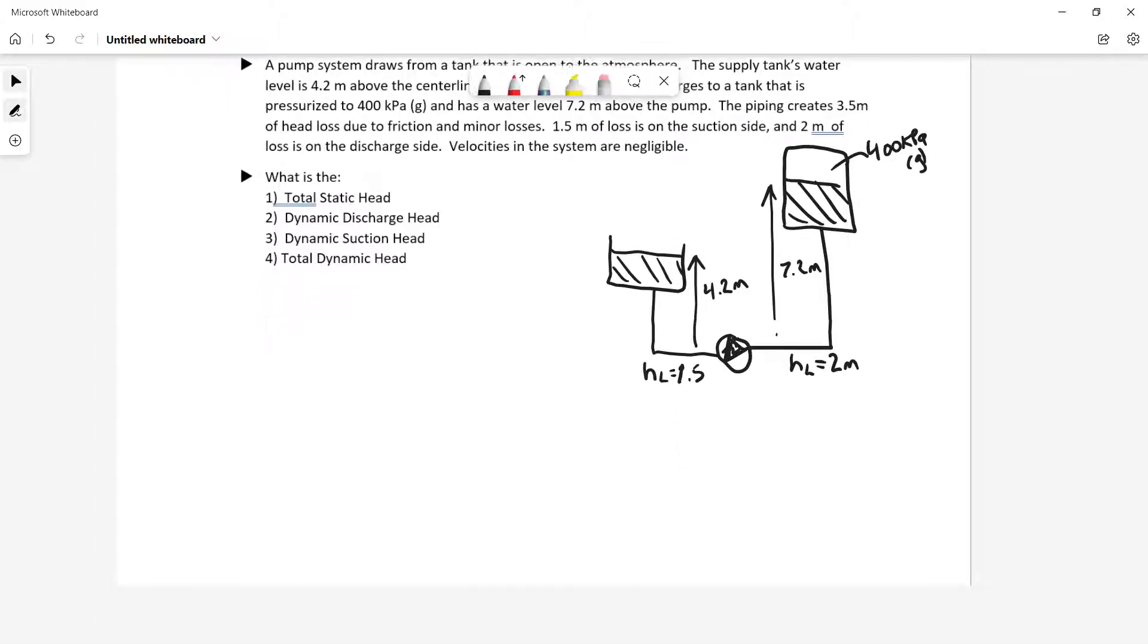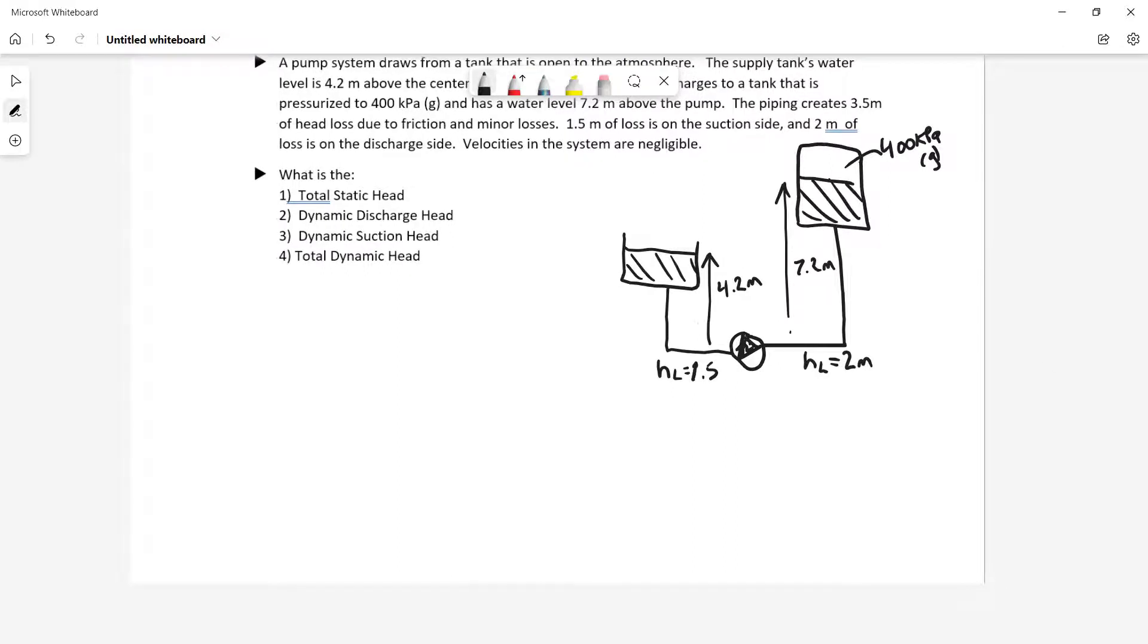So first one is the total static head. Now, let's not forget that because we have a pressurized tank, we're going to have to consider that when we calculate our total static head. So our total static head is going to be equal to the height that we have to discharge the water to. So if we consider this to be my point number 2, and I guess my point number 1, what I have is my Z2, the height at 2, plus the column of water equivalent to the pressure in that tank, so pressure 2 over rho times G, minus the height of the supply tank, Z1.